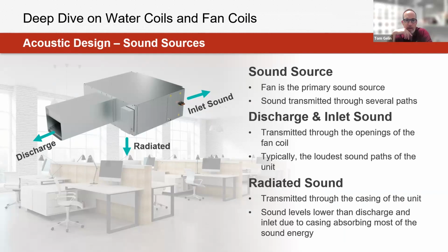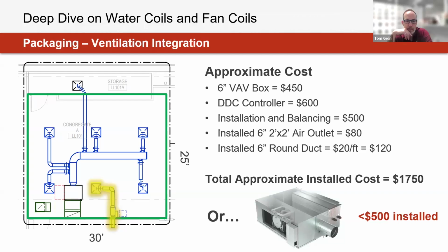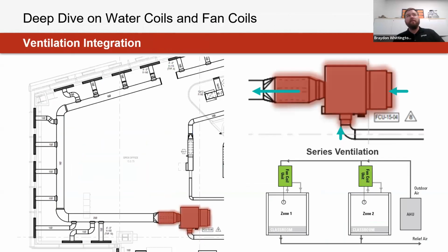Yeah, and going back a slide, Braden, or actually one more. So that could be a dry coil installation or a wet coil installation. Correct. So you could conceivably, if your DOAS unit is taking care of all the latent, you would have basically not maintenance free because you'd still have a filter and a blower, but at least as far as the condensate and cleaning goes, that all goes away, and you'd have a dry coil, which is pretty nice. Yeah.